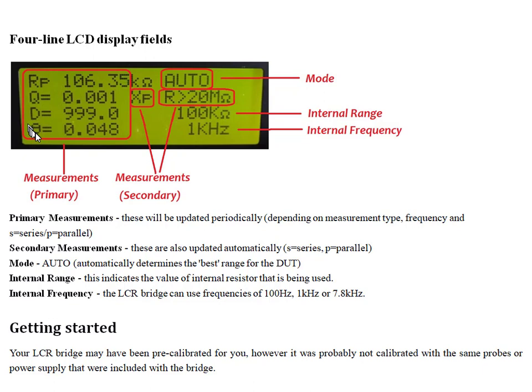So you've got the readings on the left here. RP means resistance in parallel, RS would mean resistance in series, or series resistance, and you've got the units, and then this is the mode. It could be auto, or it can be auto C, auto R or auto L, and you've got the quality factor, the phase angle, etc. The secondary measurement is shown on the second line here.